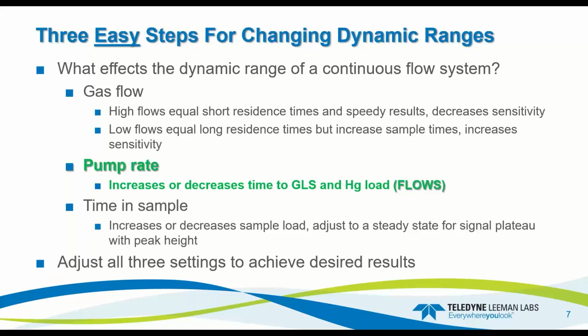So there's 3 easy steps for changing dynamic ranges. What affects the dynamic range in a continuous flow system? So it's got gas flow, pump rate, and time in sample. Gas flows, high flows are equal to short residence times. That's going to give you speedy results, but it's also going to decrease the sensitivity. But when you decrease the sensitivity, you can increase your dynamic range. Low flows or long residence time, it's going to increase the sample times, but it increases the sensitivity.